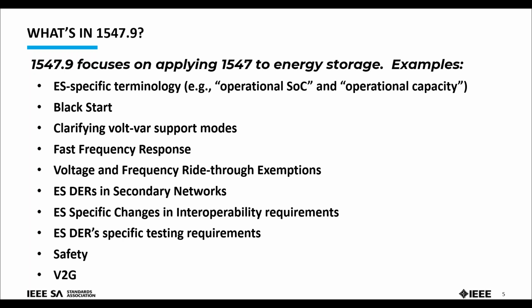There are some black start aspects—really cold load pickup is the more accurate term, though black start tends to be thrown around. You can have an intentionally islanded system energized by energy storage, and if you have excess capacity, you may want to assist in black starting some of the loads around that island. We talk about that a bit in 1547.9.